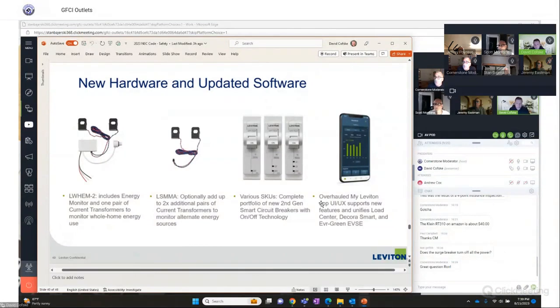Also within this Generation 2 launch that we had. Oh, here's a perfect example. On the circuit breakers, you can basically see that there's a GF, AF, GF. So those, and then way at the bottom, you'll see an off light. So on our smart breakers, if I turn the breaker off from my phone, that light will actually light up so that if anybody's looking at the panel, they'll know that somebody turned that breaker off remotely from the phone.